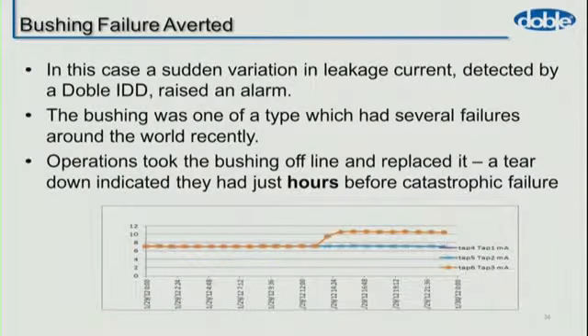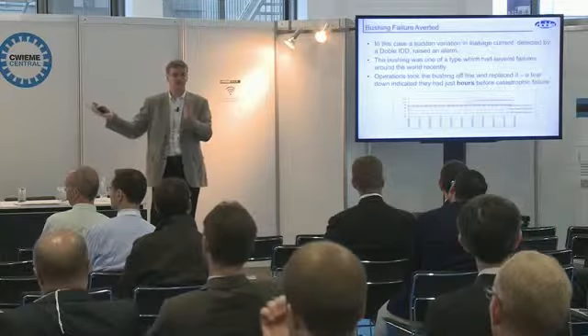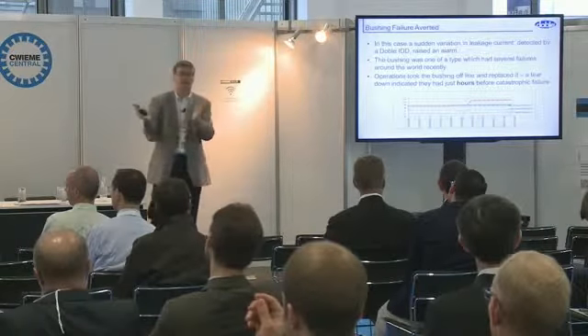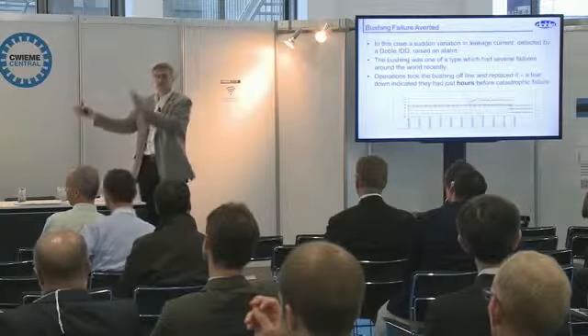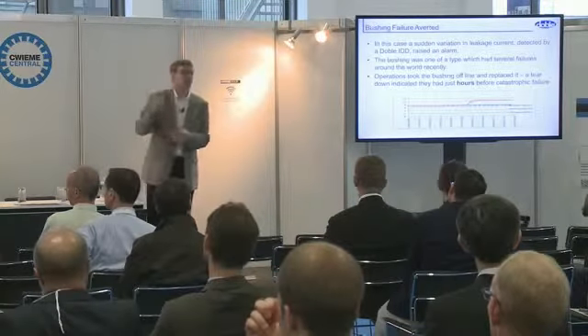The intelligence has to be recorded, written down, made available. And in this case, the operations guys on a transmission system, and trying to change a transmission system is like trying to steer a battleship. It's a big, slow thing. Once the alarm came in from the bushing monitor, they had 2 minutes to take the transformer out of service, which they did. And in the investigation, they realized that there was a lot of damage to that bushing, and it would have taken the transformer out.